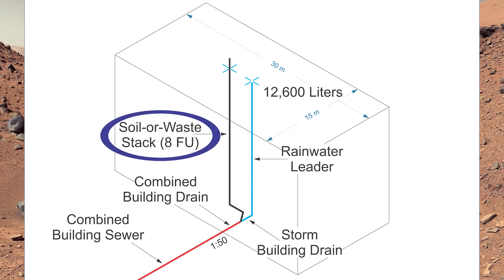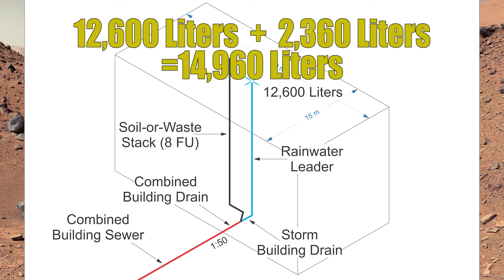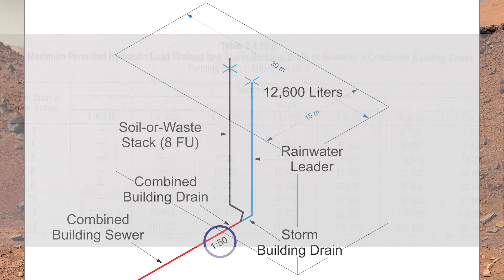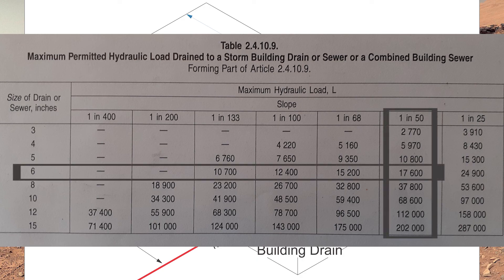Now in this example, our soil-or-waste stack is only draining down 8 fixture units. Remembering that code clause: if I have 260 fixture units or fewer, I need to account for 2,360 liters to be added into the combined building drain. So: 12,600 liters plus 2,360 liters equals 14,960 liters draining into the combined building drain. It has a grade of 1 in 50, so I look to table 2410.9, go down the 1 in 50 column, and at the correct liter load it looks like I am six inches.